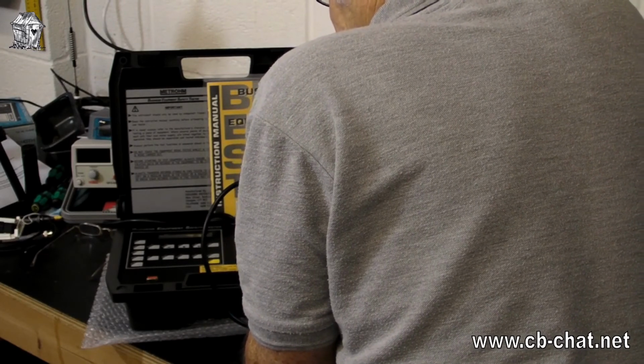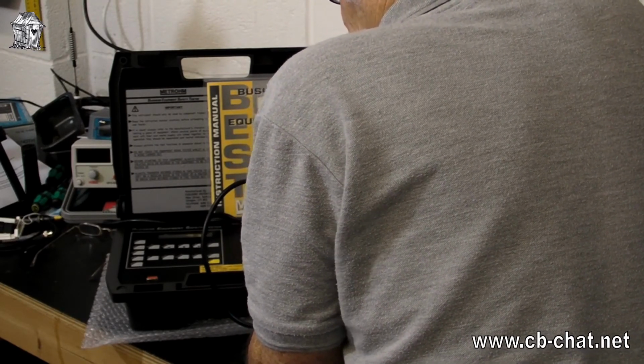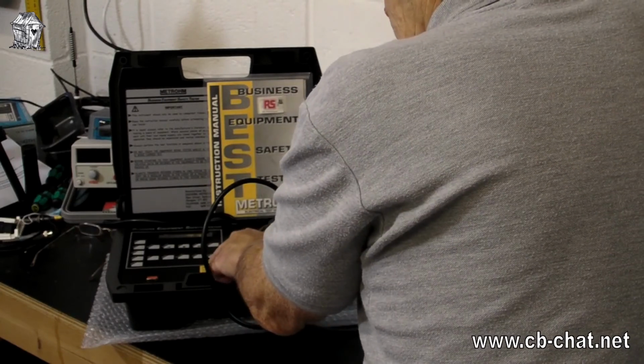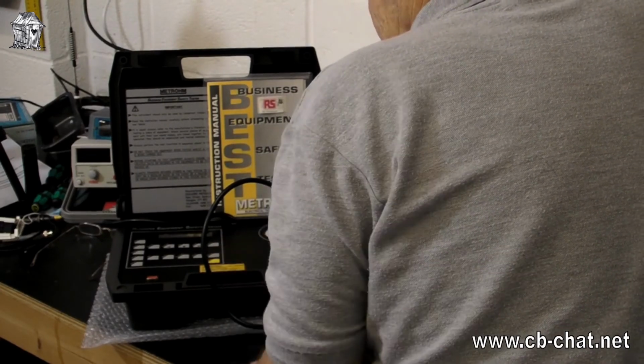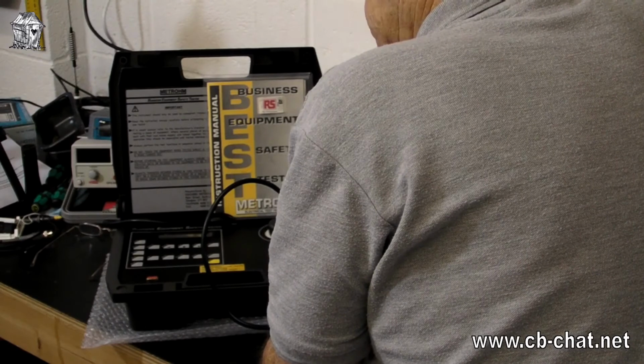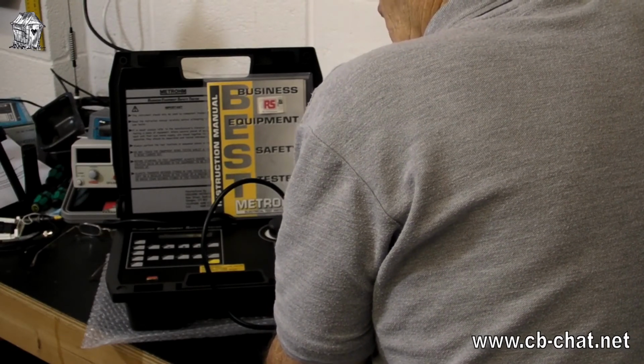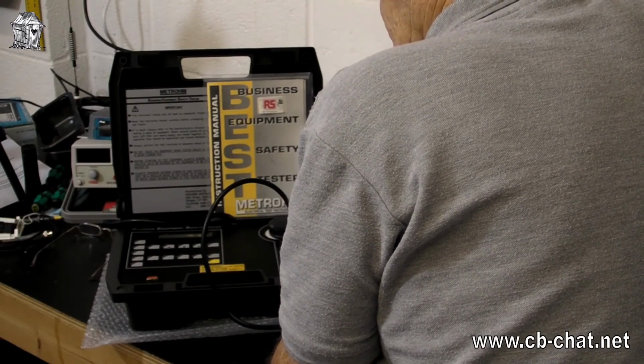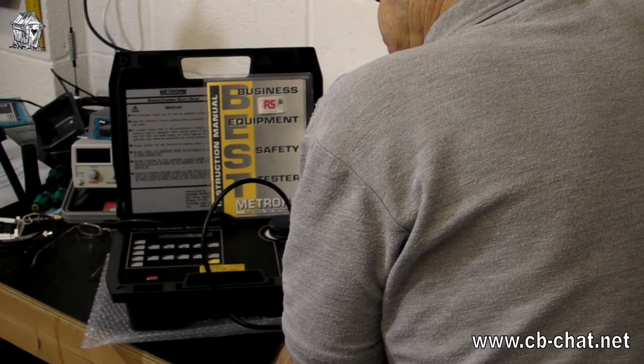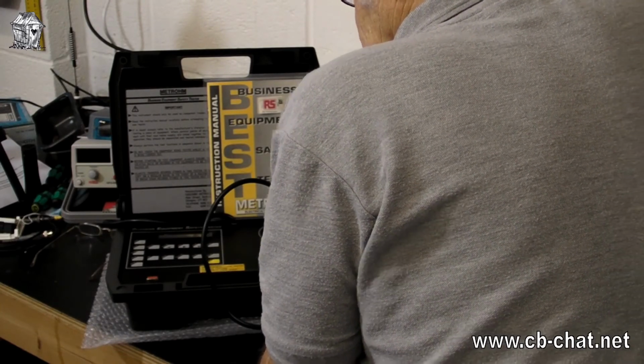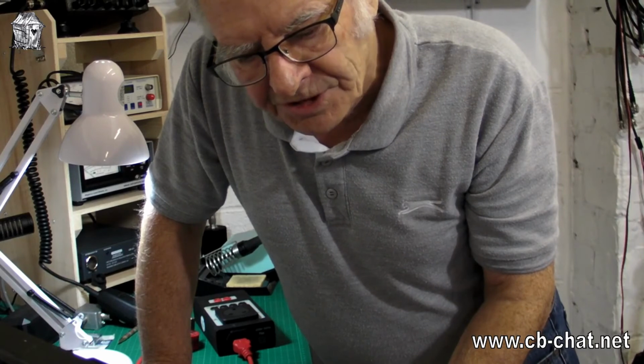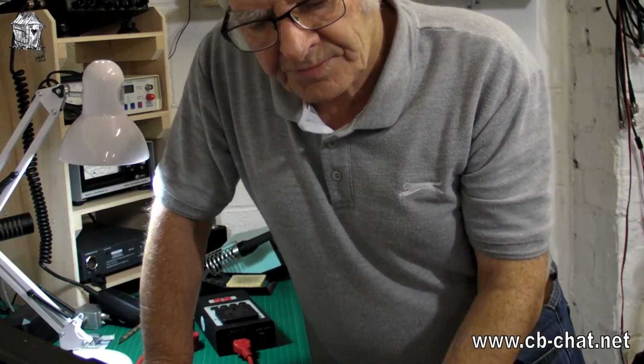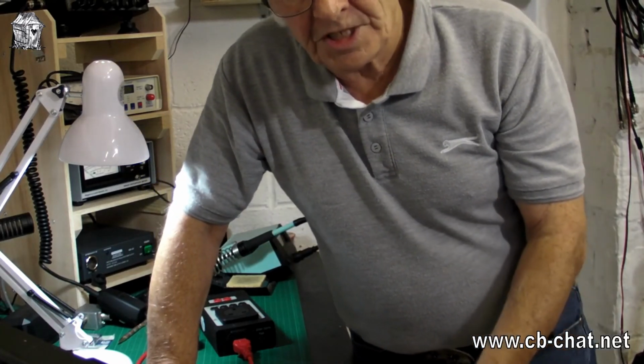Everything's tested. Now it's saying press execute for earth test. So we'll now check the earth continuity. Press that. It's testing the earth now, to make sure that the earth connection is working on this particular lead. And it says no earth. So there we are, it's a faulty lead, no earth.